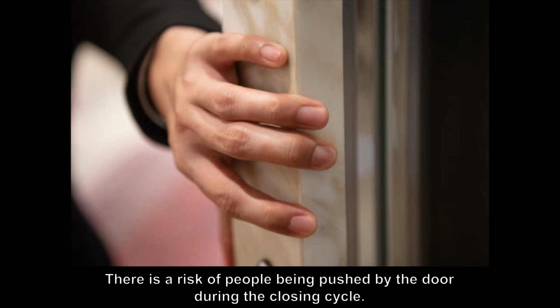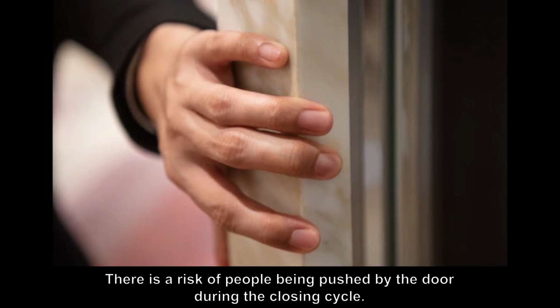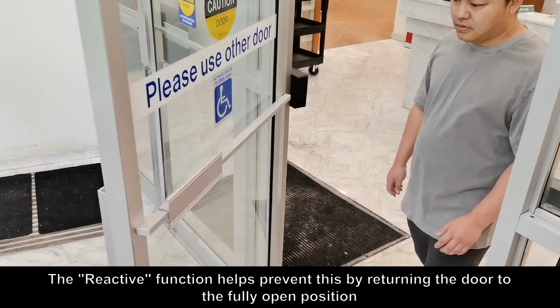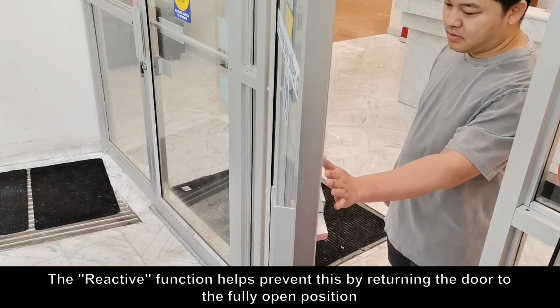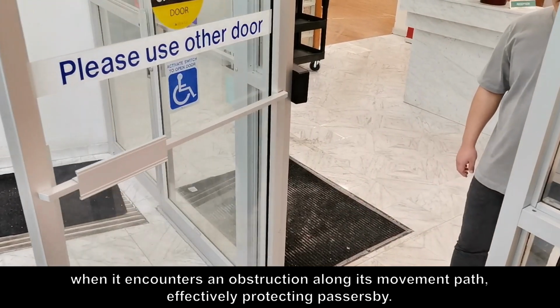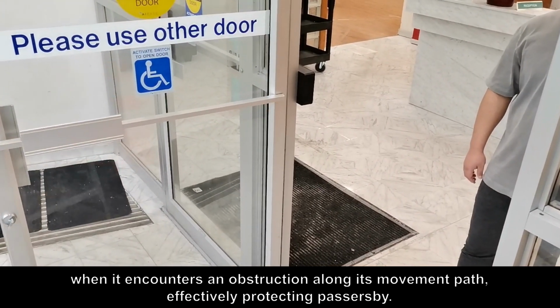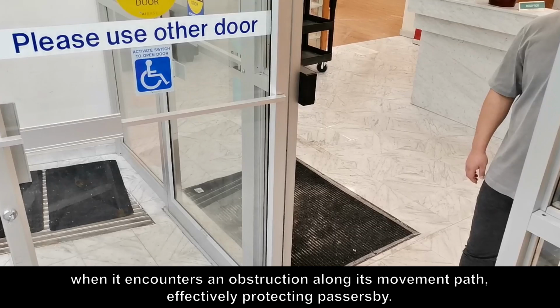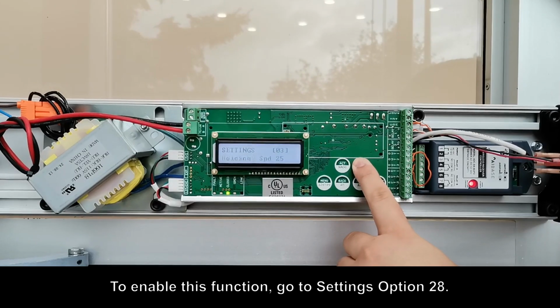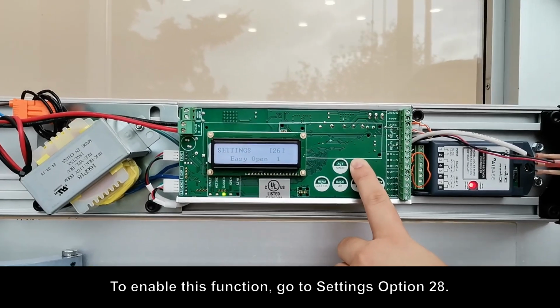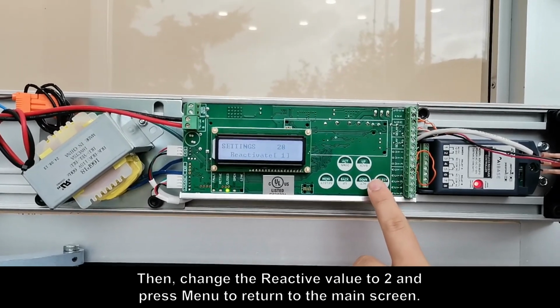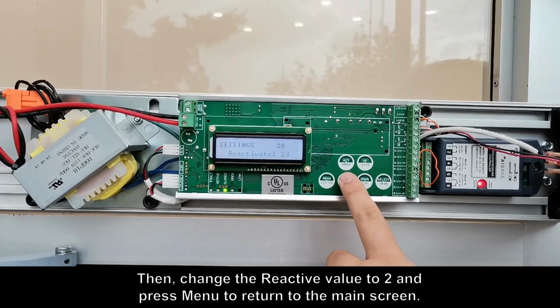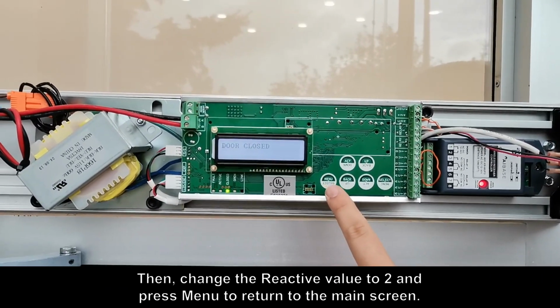There's a risk of people being pushed by the door during the closing cycle. The reactive function helps prevent this by returning the door to the fully open position when it encounters an obstruction along its movement path, effectively protecting passersby. To enable this function, go to Settings option 28. Then, change the reactive value to 2 and press Menu to return to the main screen.